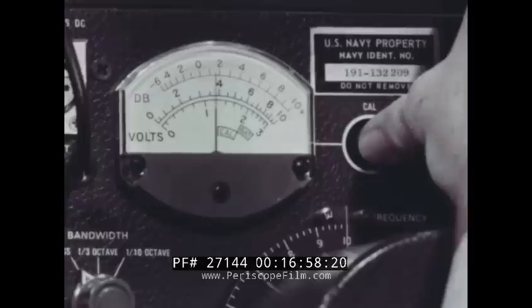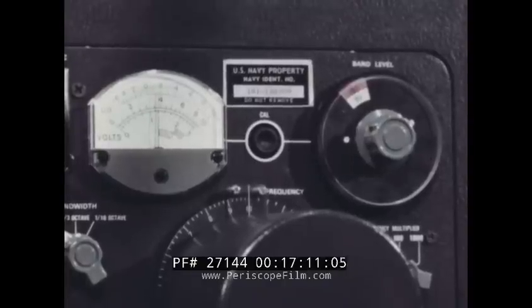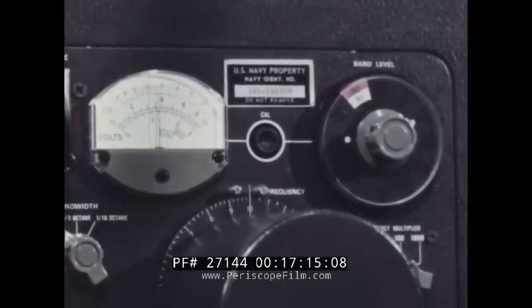Now, here's an important item that often leads to confusion. You have just calibrated the analyzer to match the reading of the sound level meter, 91.7 dB. But the 90 part of that figure does not show on the analyzer dials. You must remember throughout the data taking that the outer dial of the analyzer corresponds to 90 dB. We'll review that in a moment to be sure you've got it.